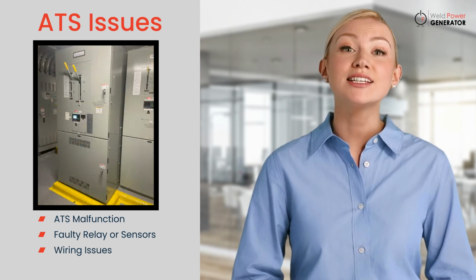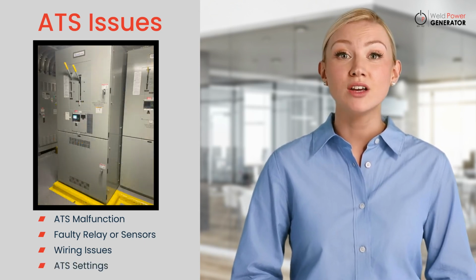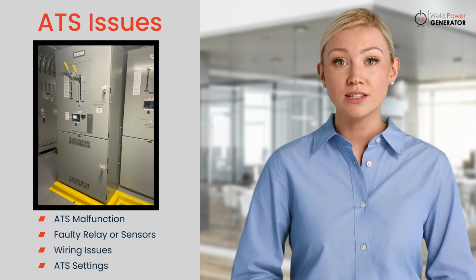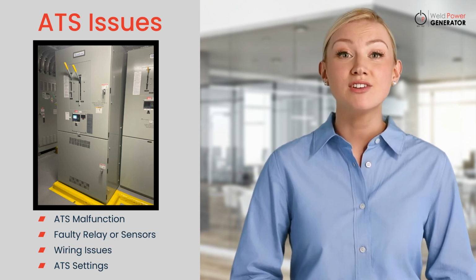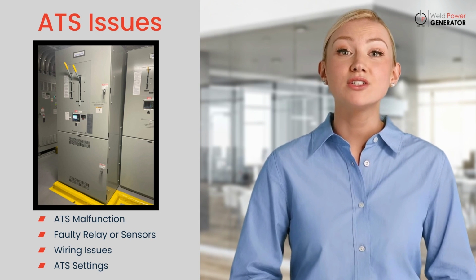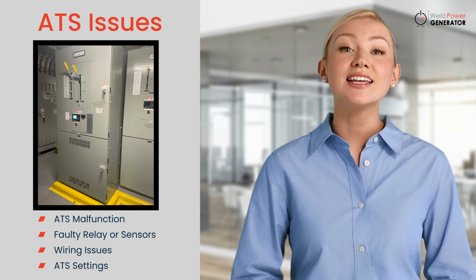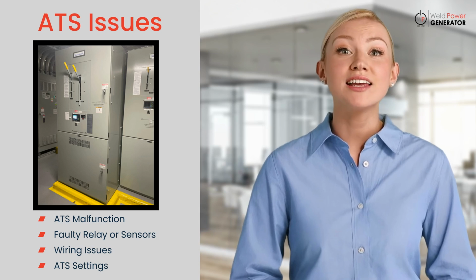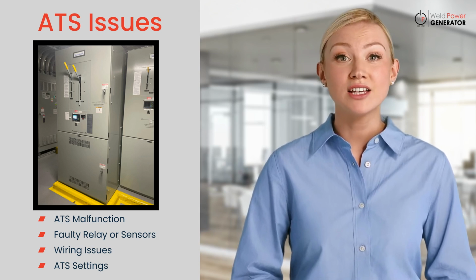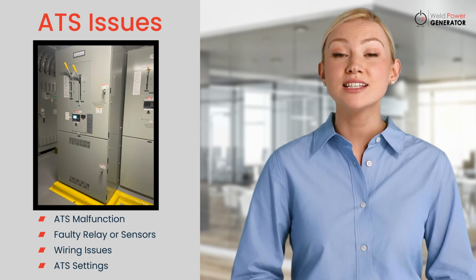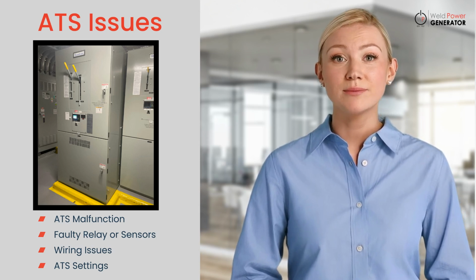Some ATS units have settings that allow for load testing or specific operational preferences. If an ATS is configured incorrectly, it could cause the generator to start unexpectedly. Checking the ATS programming and ensuring that the settings match the facility's intended operation can prevent unnecessary generator starts.